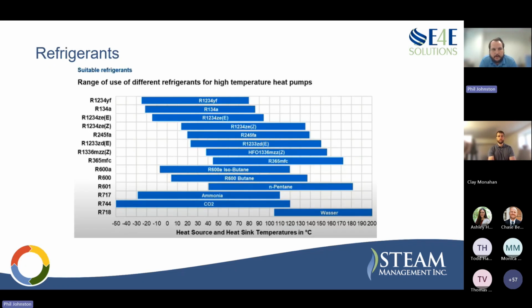I touched on this a little earlier, but it's important to revisit. So, the refrigerant drives the circuit going through that compressor, going through that condenser and evaporator. What refrigerant you use is very important from a performance standpoint. Ammonia and CO2 are very popular natural refrigerants. Ammonia has that safety factor to it, like I said, but it is very efficient.